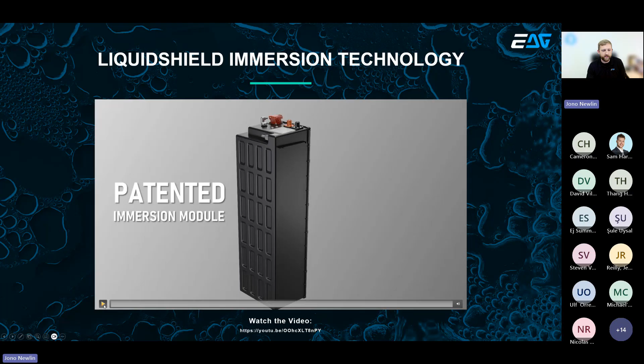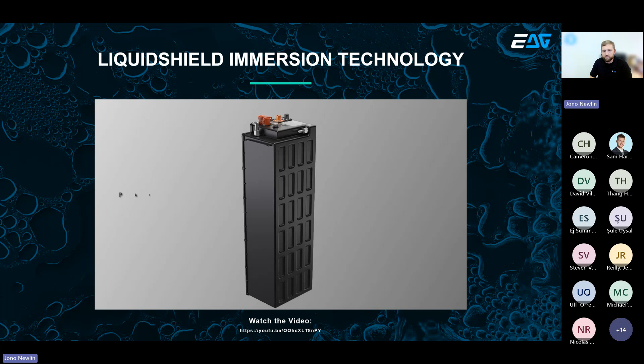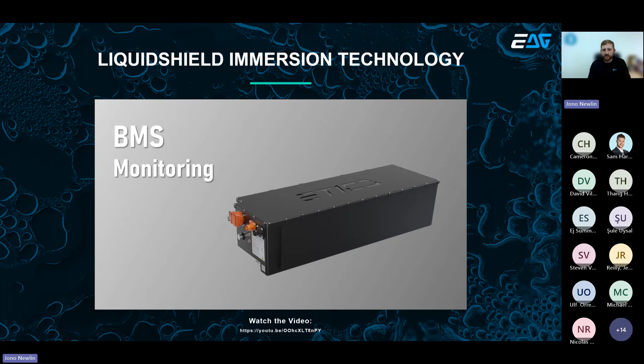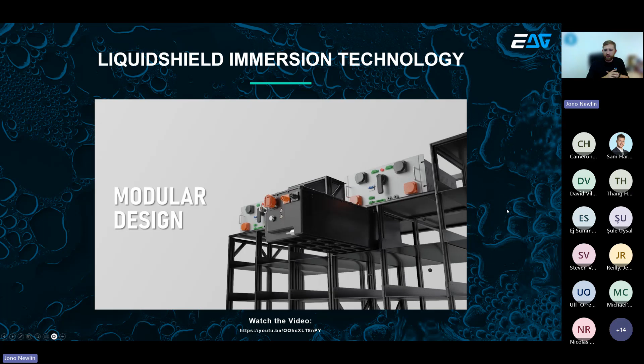This is a good visual, and this is our product, how we designed it, just to give you an idea of how this can be implemented. So this is our module. This has LFP cells, 20 cells in this particular design. And as this cutaway shows, all of the bus bars and all of the cells are submerged in that liquid. So that single container is filled with liquid. It's a liquid bath. And then in there, it's built into the racking system. We have a reservoir on the bottom that circulates additional liquid throughout.